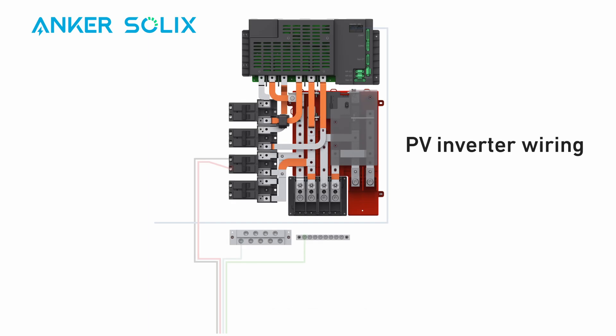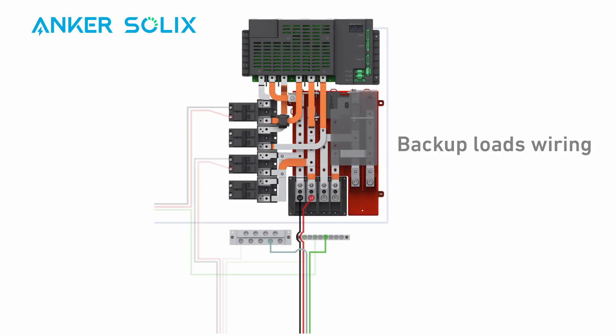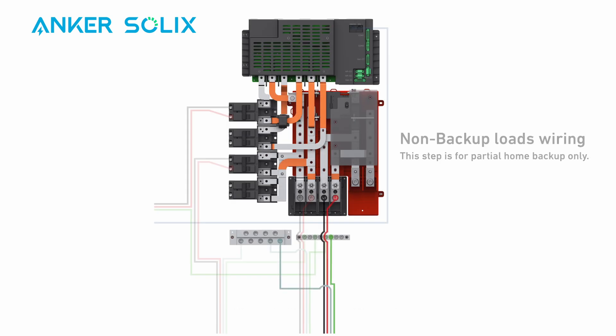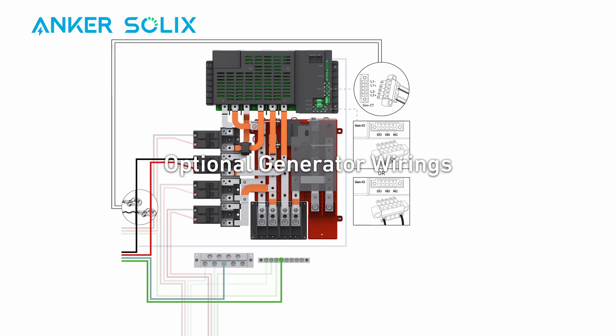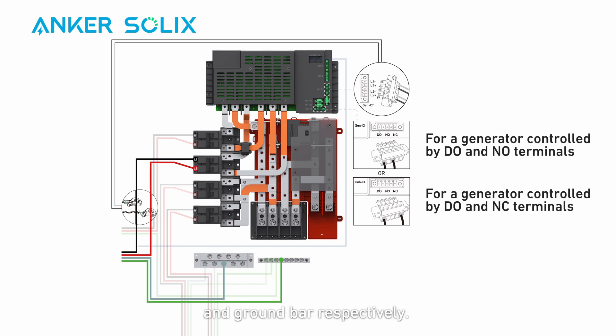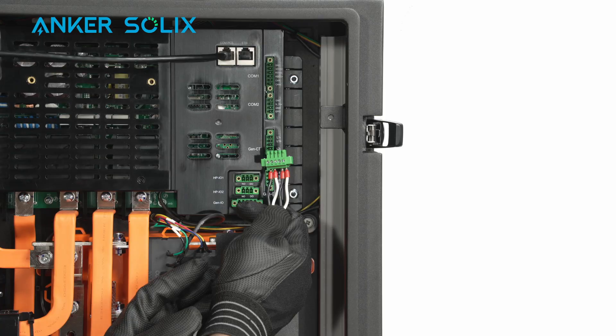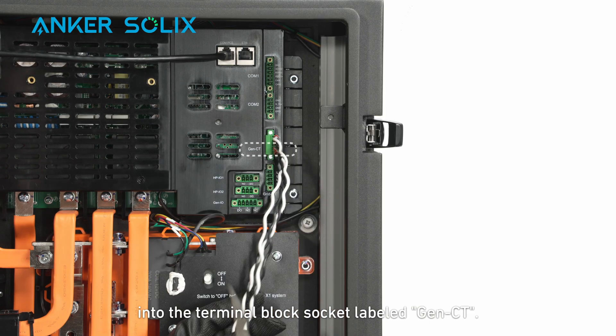Connect the key panel wiring sections: PV wirings, backup loads wiring, and non-backup loads wiring. For generator wiring, put a generator breaker on the rail labeled generator and secure the breaker using an M3 screw. Land the neutral and PE cables on the neutral bar and ground bar respectively. Connect the L1 and L2 cables to the L1 and L2 poles of the generator breaker. Orient the current transformers with the arrows pointing towards the generator. Plug the terminal block connector into the socket labeled Gen-CT.